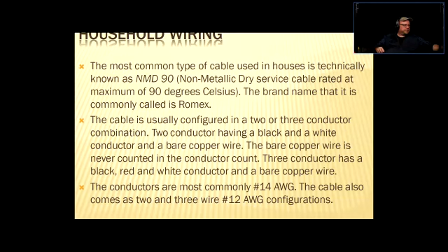So NMD90 is a common cable - non-metallic, dry, up to 90 degrees Celsius environment. The cable is usually configured as a 2 or 3 conductor combination. 2 conductor has a black and a white, which we talked about, and a bare copper wire. The bare copper wire is never counted as a conductor in the conductor count - we just talked about that. 3 conductor has a black, red, and white conductor and a bare copper wire. The conductors are most commonly 14 gauge. The cable also comes as 2 and 3 wire in the 12 gauge configuration. Yeah, a bit of a mouthful here.